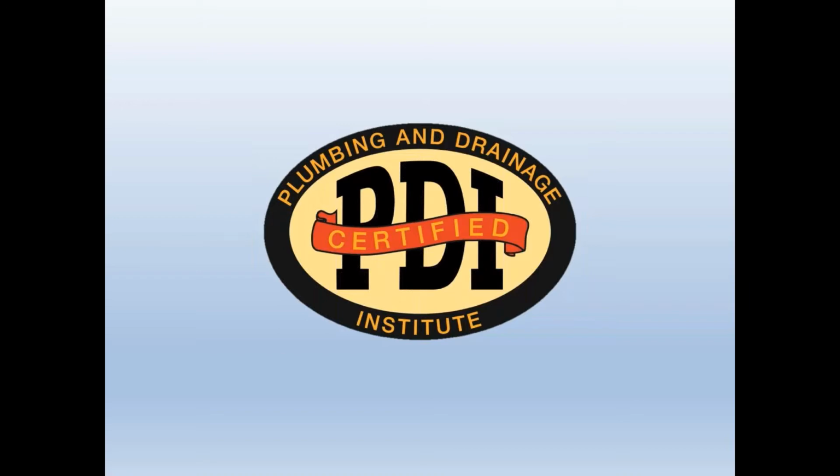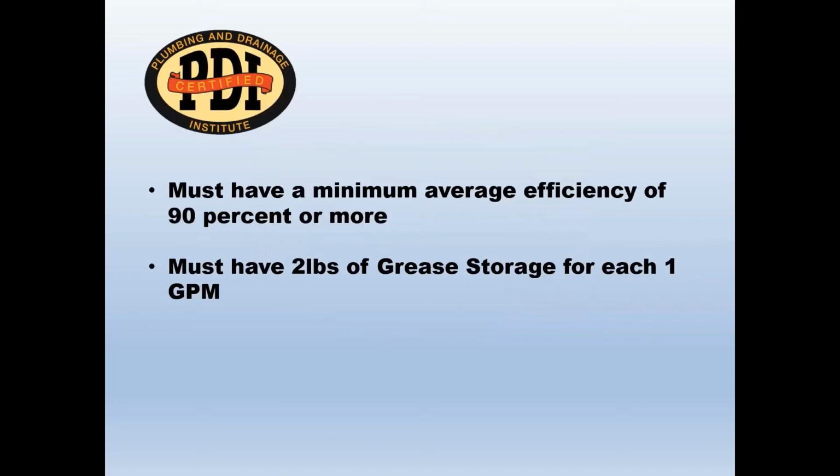It really touches on a couple key things. Two of those: it must have a minimum average efficiency of 90% or more to meet this standard. It also, with your grease interceptor, you must have 2 pounds of grease storage for each 1 GPM.